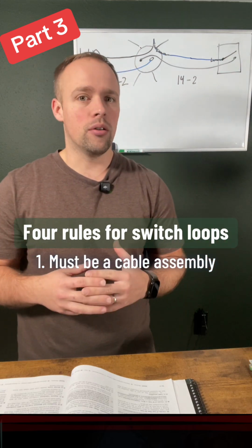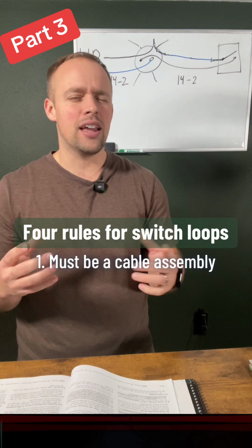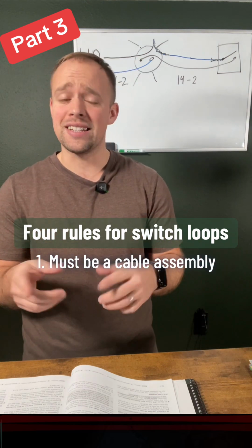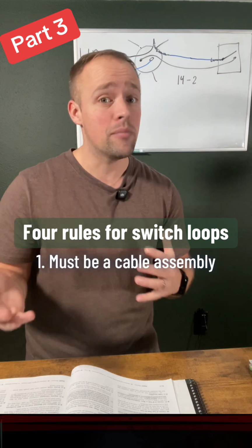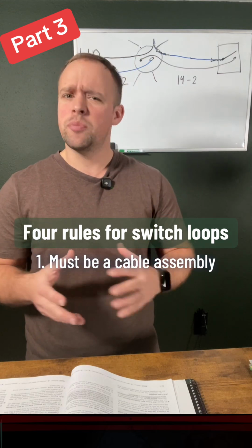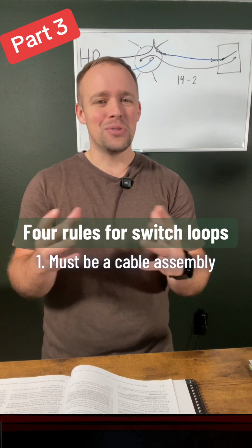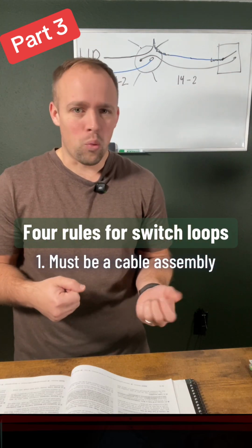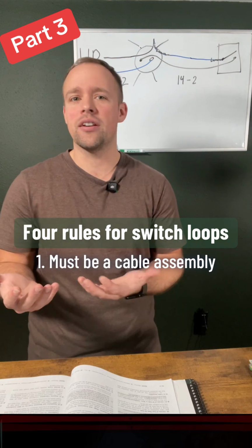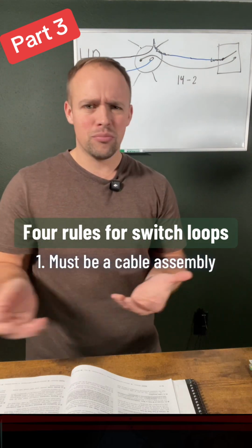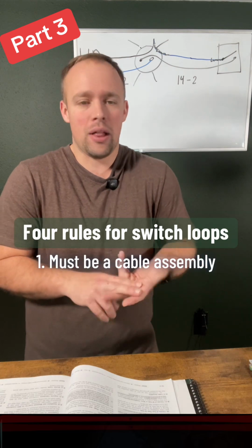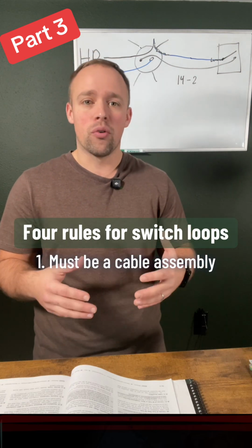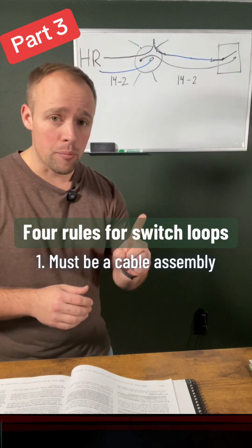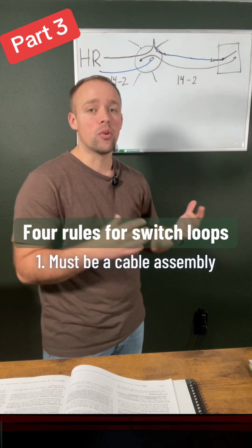Okay, so I mean, if you tried a switch loop using some other method that's not a cable assembly, like, I don't know, EMT conduit or PVC conduit, the inspector is going to be like, why the heck did you do that? Just pull the white insulated wire and make that your grounded conductor. Or pull a different color, a red one, a black one, a blue one, whatever the case is, for your ungrounded conductor. So rule number 1 for switch loops is that you can only do it for a cable assembly.